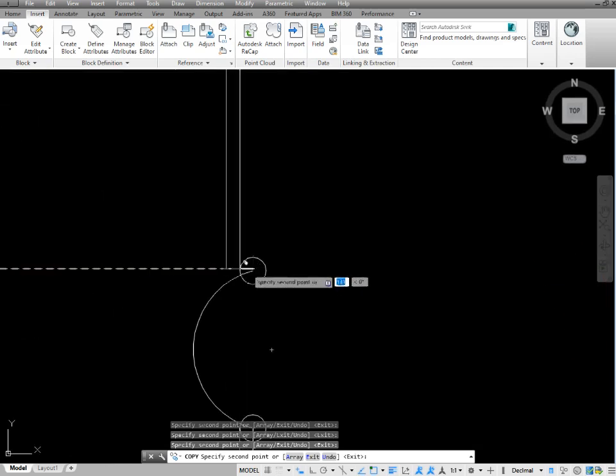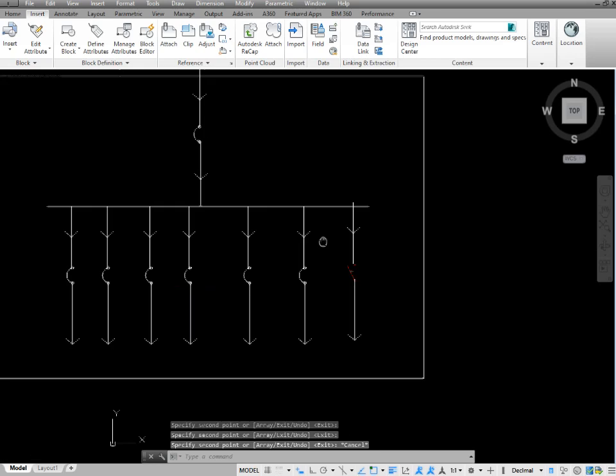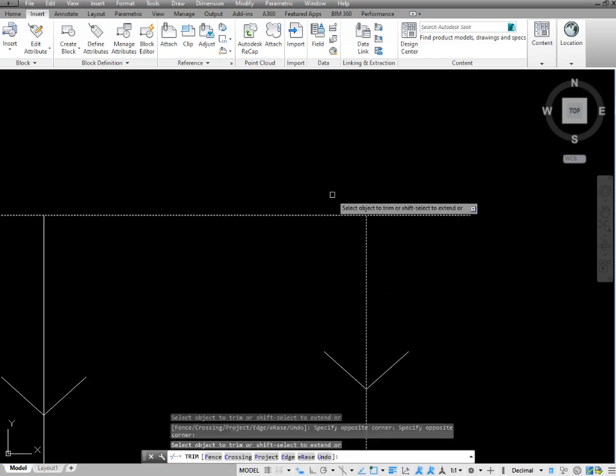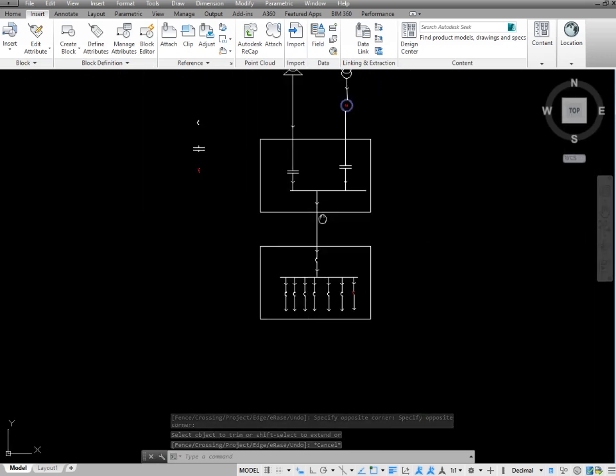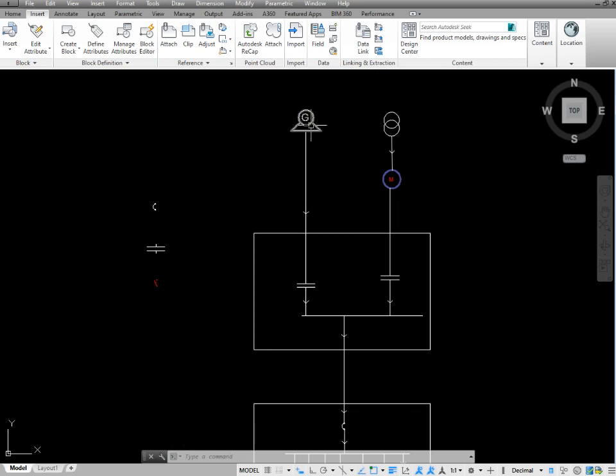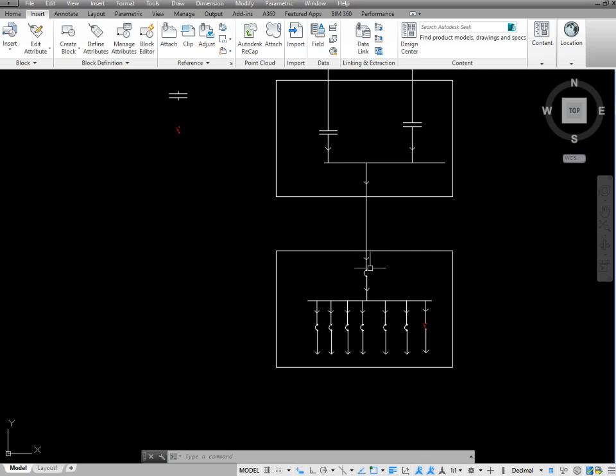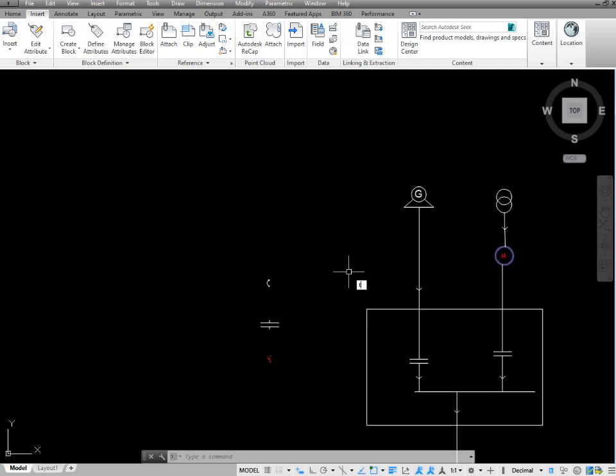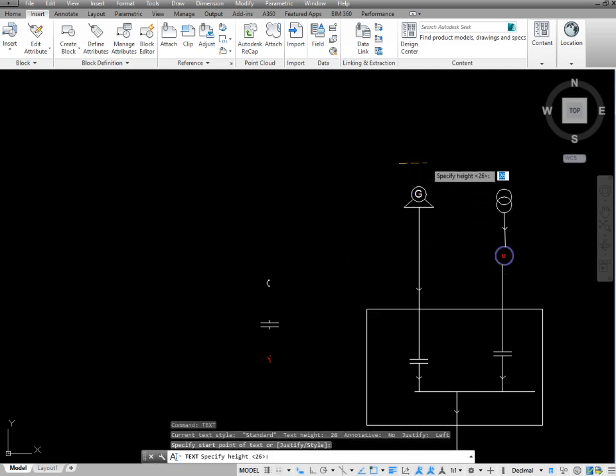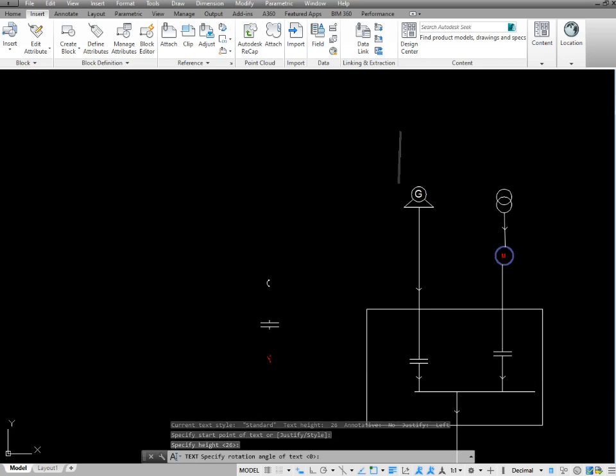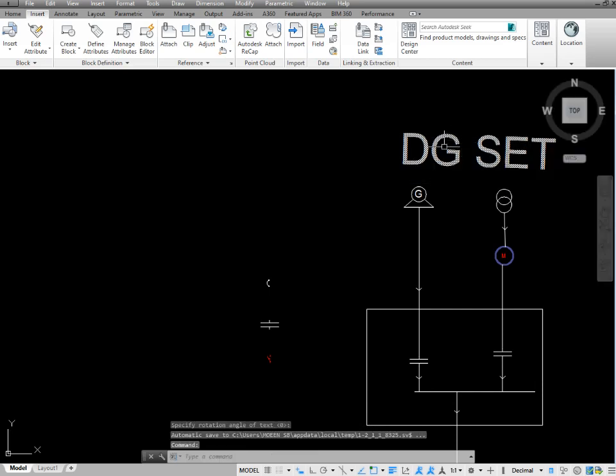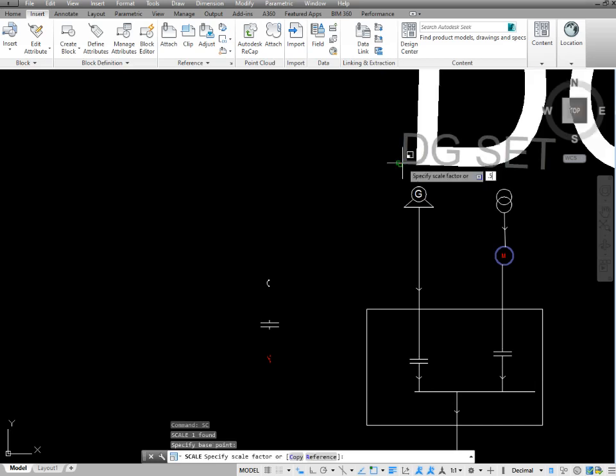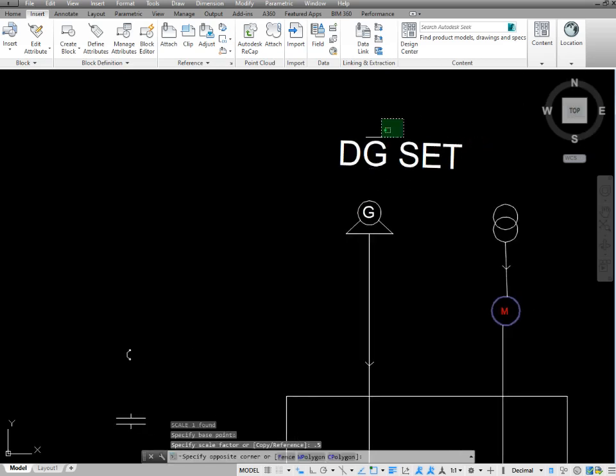I have drawn a complete single line diagram. Now I trim the connection point — press TR Enter, select both items, and simply click. I have now drawn a simple complete layout: the transformer and generator both supplies are coming into the ATS panel, and from the ATS panel the supplies are going to the home DB or office DB. Now I need to add text. Simply take the Text command, press Enter, place the starting point and endpoint, and add the label. This supply is labeled as the generator DG set. Simply scale it down — press SC Enter and scale by 50%.